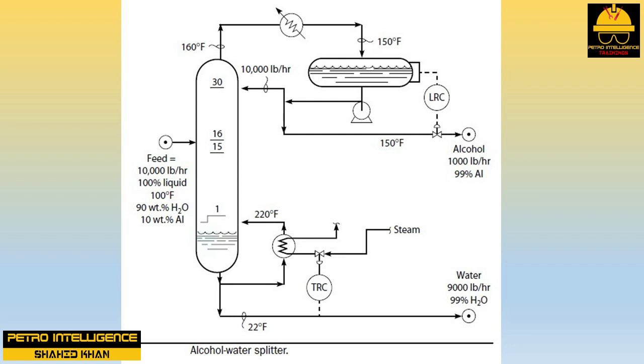The flow of vapor leaving the top tray of the tower is equal to the flow of reflux plus the flow of the alcohol overhead product. The overhead condenser heat removal duty is proportional to the reboiler heat duty. The weight flow of vapor in a tower is controlled by one factor and one factor only: heat. An increase in reflux rate, assuming the reboiler is on automatic temperature control, increases both the tray weir loading and the vapor velocity through the tray deck.